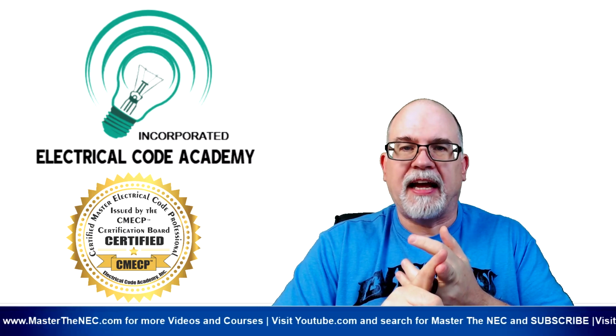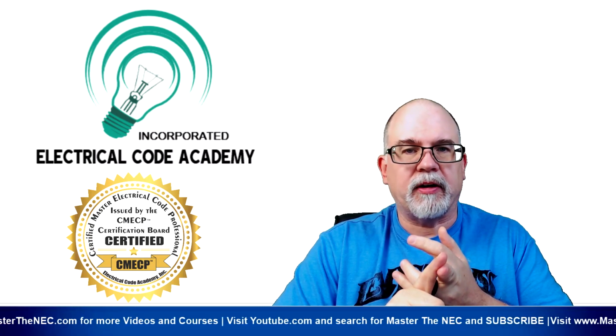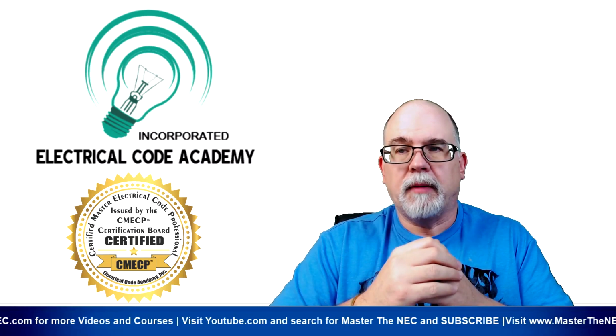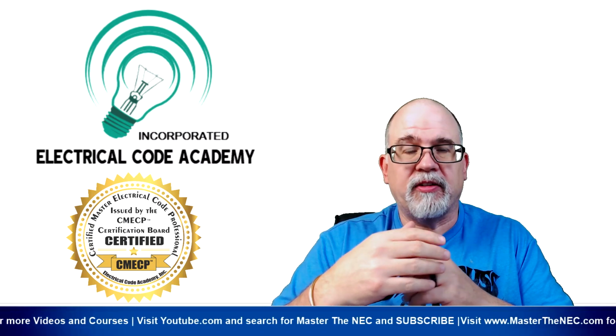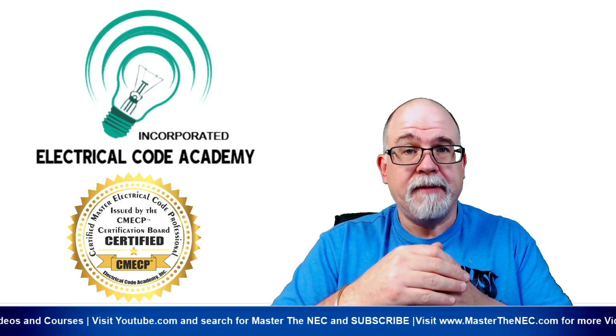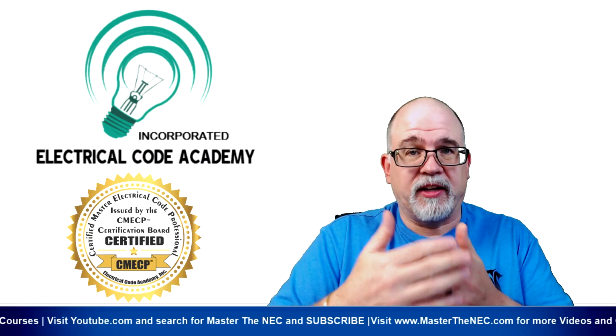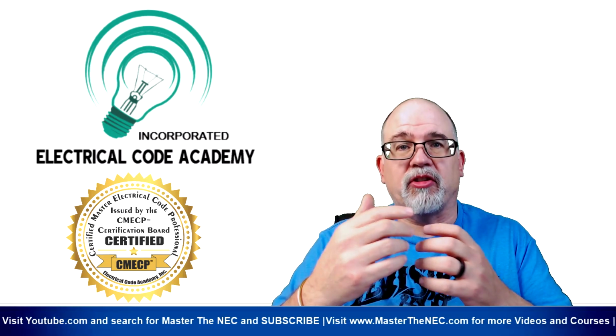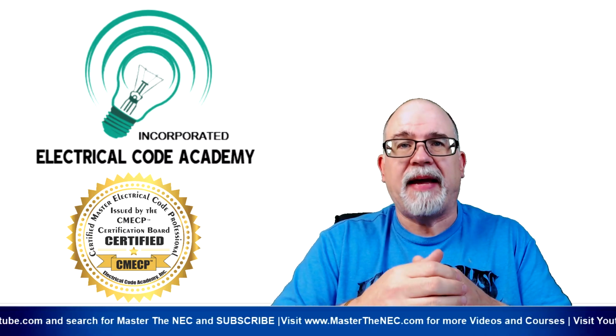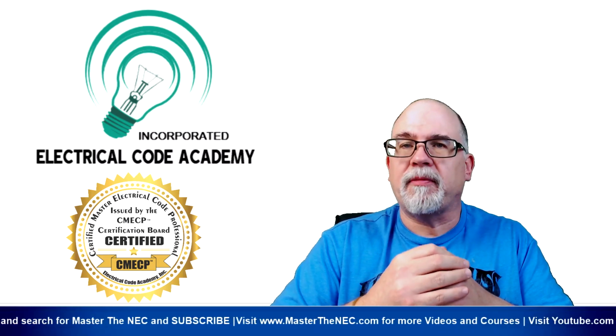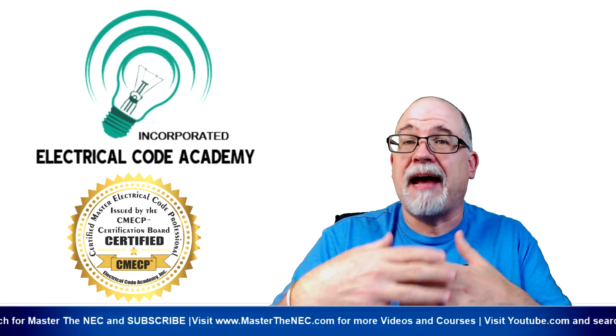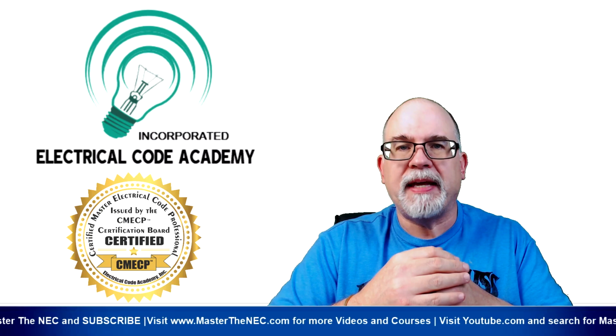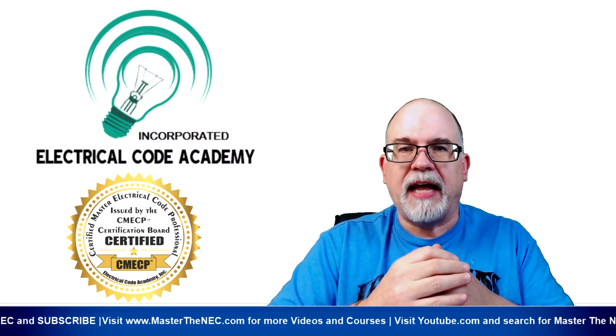Definitely learn how to size the overcurrent protection for the primary and secondary of the transformer. Watch that series and then understand in part 3 where you're sizing the conductor, and understand that you have to protect the conductor at its ampacity. However, we do have some beneficial things that come in tap rules under 240.21(B)(3). You've got to go back and watch that.